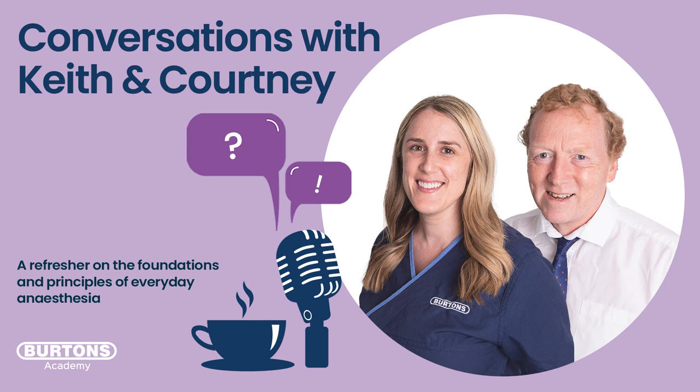So placing the cuff correctly, with the right cuff selection and in the right position, hopefully gives us a good signal. During anaesthesia, we can set the machine on automatic mode — every two or three minutes it repeats a reading, with the appropriate cuff size set on the machine. The position of the cuff relative to the heart does have a big impact, and if there's a difference we have to compensate for it. We're now getting to the point where we can get a reading and start to do something with it.